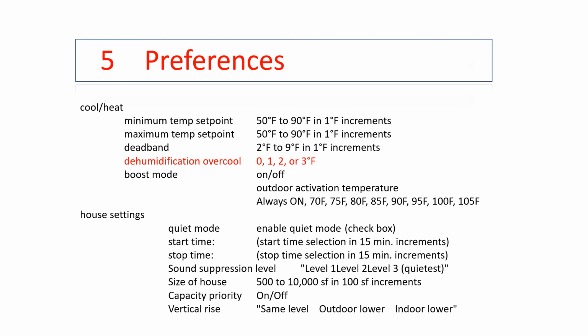We'll also see cool heat under preferences. And here's what we'll do, our minimum and maximum set points. Here's where we'll find our dead band if we're set on auto instead of manual changeover. And our dehumidification overcool. Keep in mind, if you have turned on dehumidification, under high humidity conditions we are slowing the fan down, but when it meets demand for the thermostat, it shuts off. This allows it to overshoot your demand if you still have high humidity present. Once it meets humidity demand, it goes back to the set point and will not overshoot.